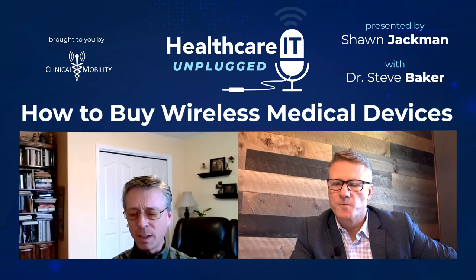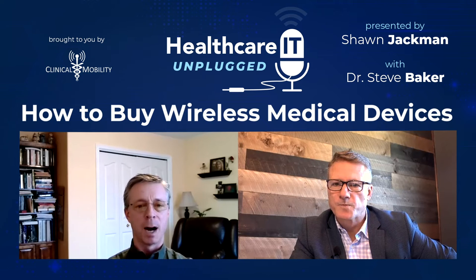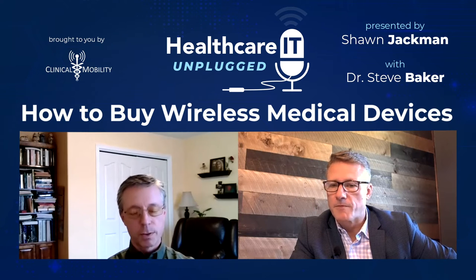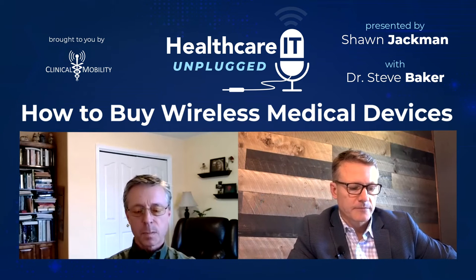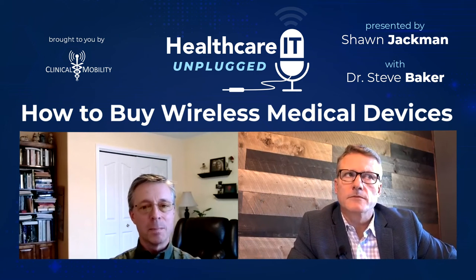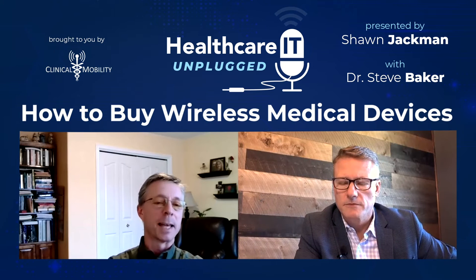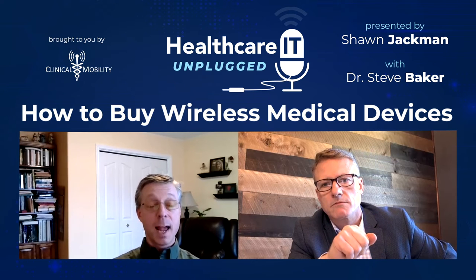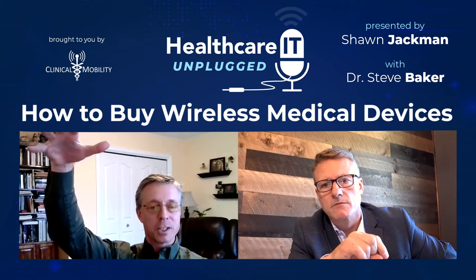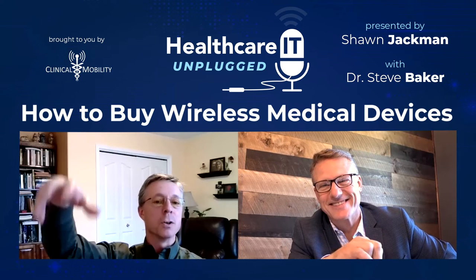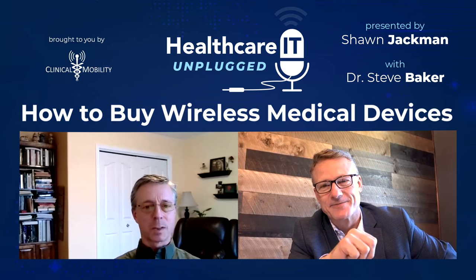Now, I changed my radio driver to mitigate a bug, a security vulnerability. Well, if you change the radio driver, you should probably do some verification and validation testing to make sure the system still meets its intended use—basic radio quality assurance, fair? Yeah, but that doesn't meet the level of a 510K. Usually what it is, is called a letter to file. You put a letter in the design history file saying this change was made. And there are times where if you get a big enough stack of changes, the FDA will strongly suggest you do a new 510K.